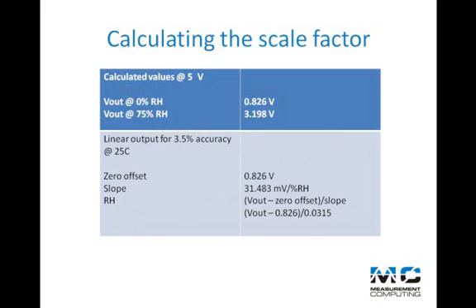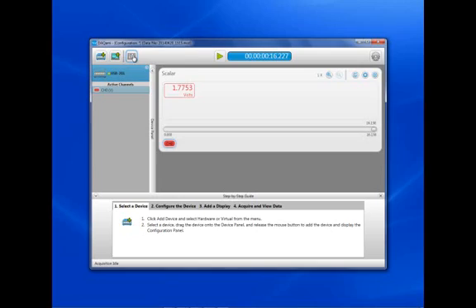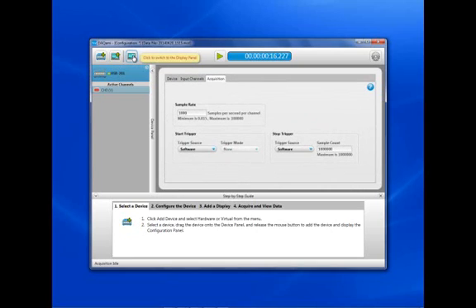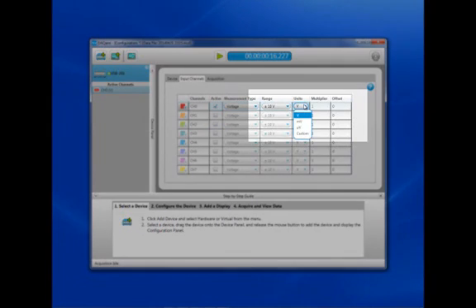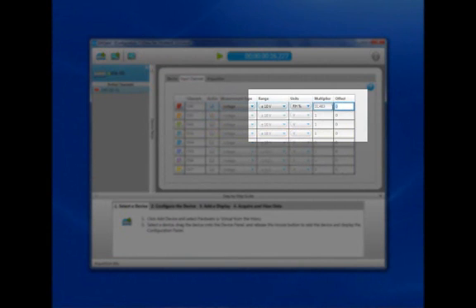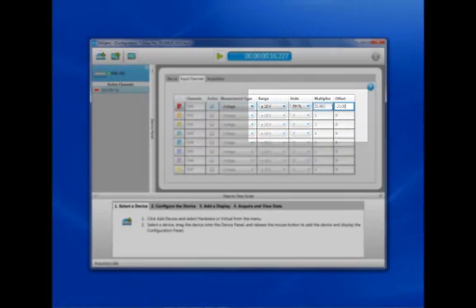Now, we just need to enter them into our formula in DAQAMI. And to do so, we need to switch to the configuration panel. After that, pull down the units menu and select custom. Type in RH percent sign for relative humidity, then add your scale factor values.